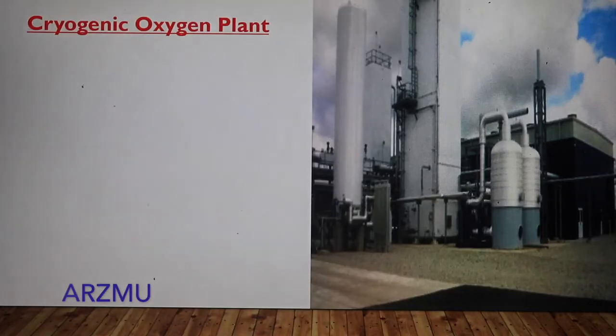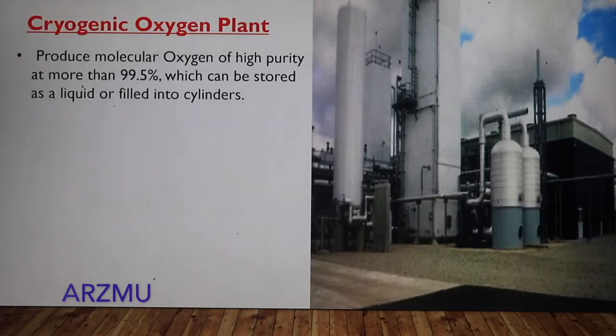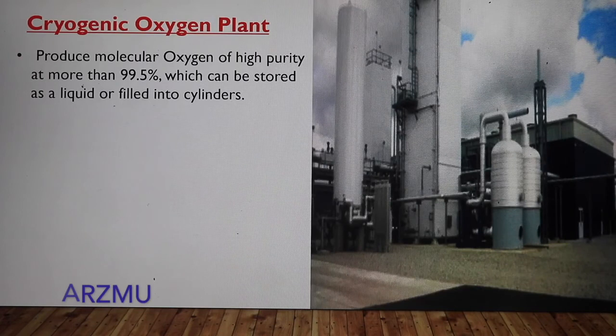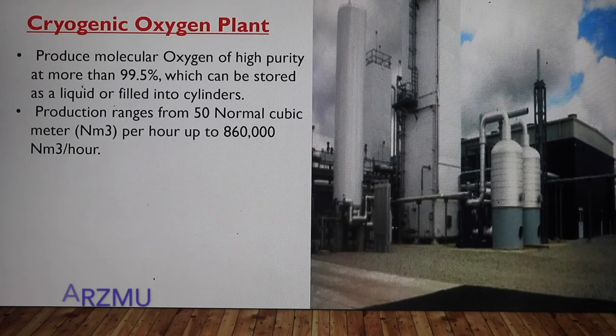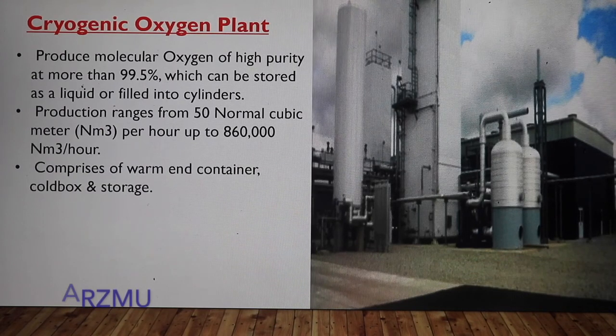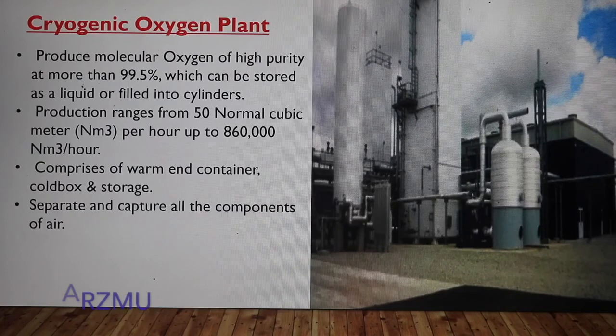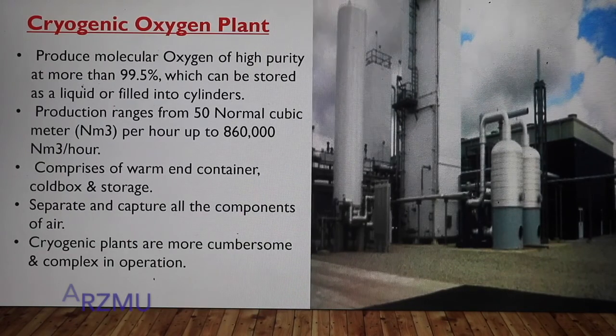Now a short description about a cryogenic oxygen plant. A cryogenic oxygen plant produces molecular oxygen of high purity at more than 99.5%, which can be stored as a liquid or filled into cylinders. The production of cryogenic plants ranges from 50 normal cubic meters per hour to 860,000 cubic meters per hour. The cryogenic oxygen plant consists of a warm end container, cold box, and storage. Cryogenic oxygen plants separate and capture all the components of air, but are more cumbersome and complex in operation.